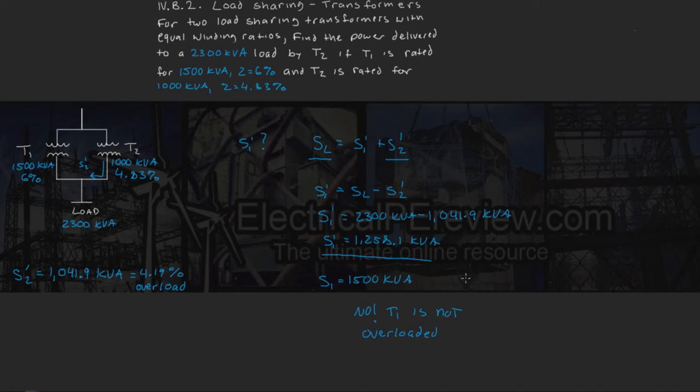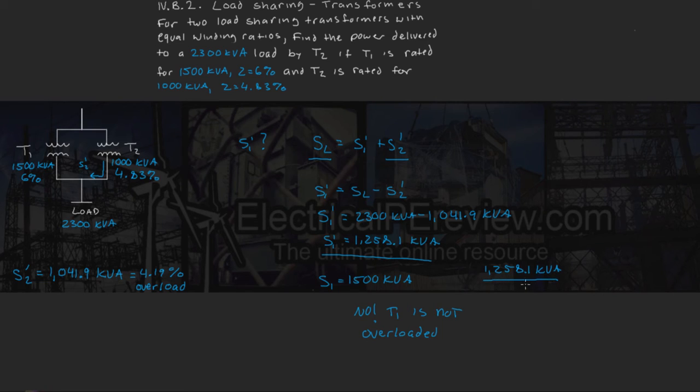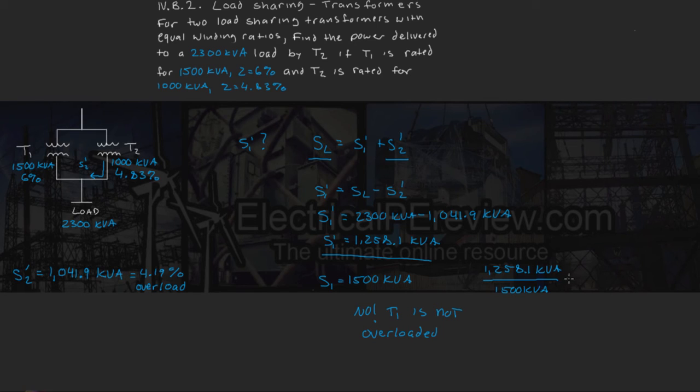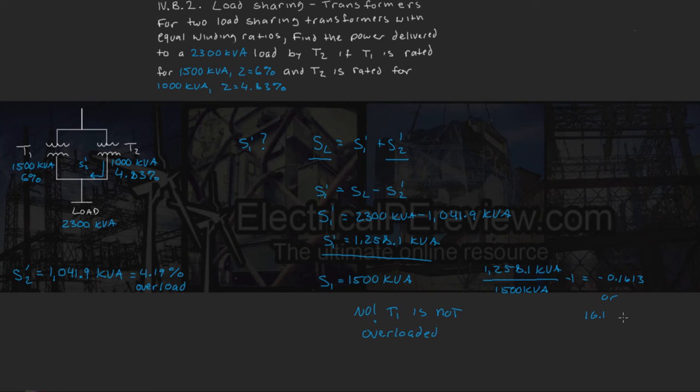In fact, if we want to find the percentage that it is loaded, we could do the same math of 1258.1 kVA divided by its actual rating of 1500 kVA minus 1 gives us a negative 0.1613. Multiply that by 100, and we come up with 16.1% underloaded.